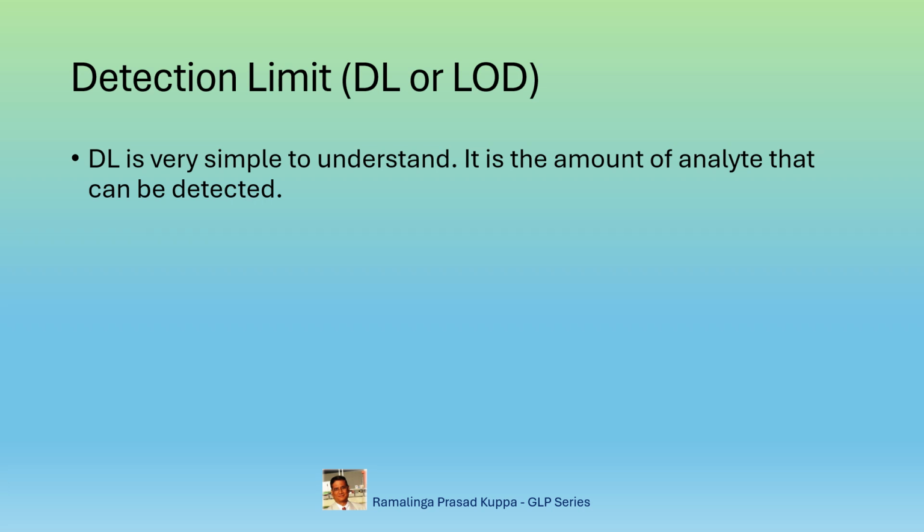In HPLC analysis, the baseline is not straight. There are minor fluctuations. The range of fluctuations is so narrow that you are not sure whether there is any response due to any impurity. Anything more than the disturbance, which is called noise in HPLC terminology, is considered as a response due to impurity. The small response may be 2 or 3 times the average response range.